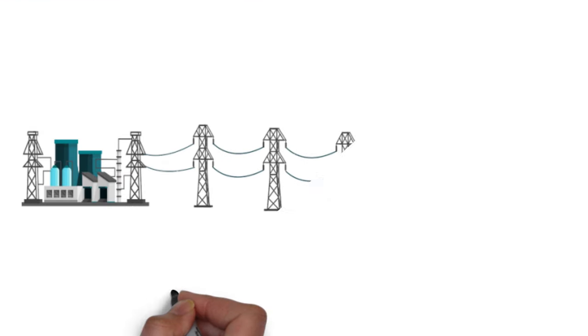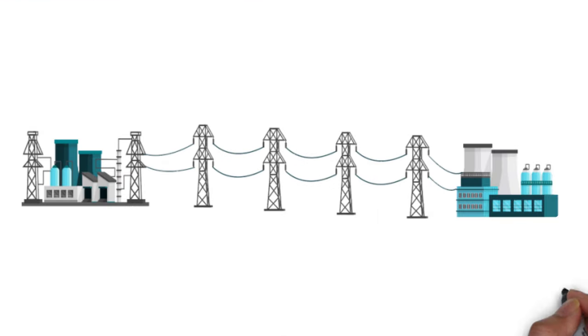If we consider the example of two power stations connected by a transmission line of arbitrary length, both plants have synchronous machines. If one of the machine's angular displacement exceeds 90 degrees it will likely cause the generator to lose synchronism and risk the stability of the line.